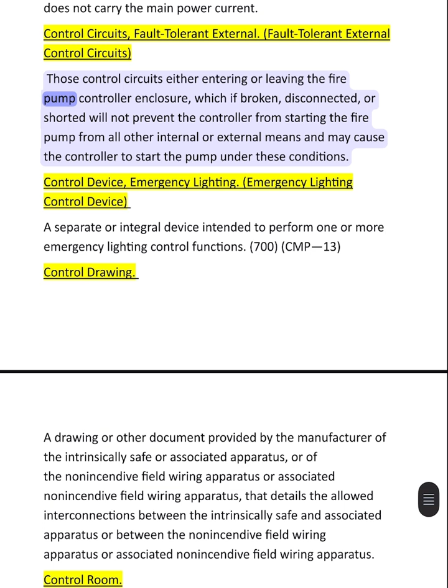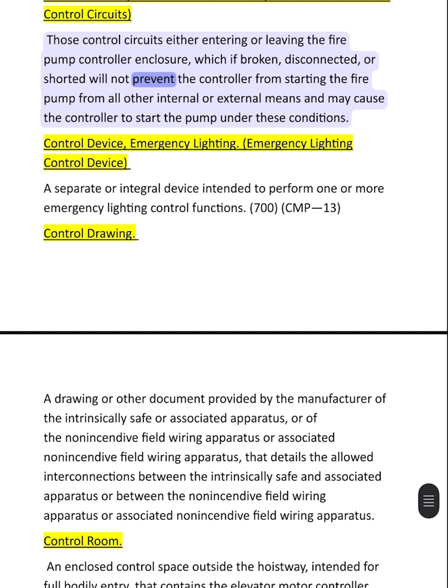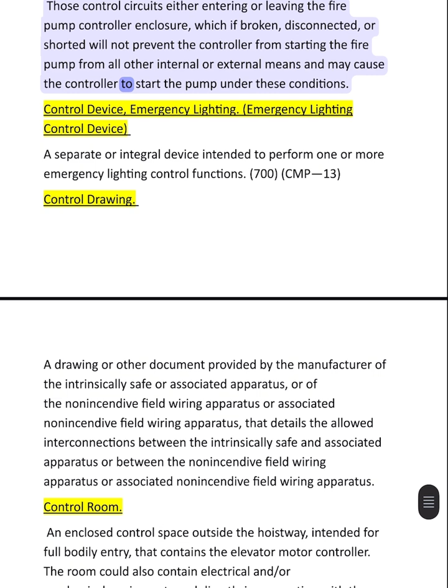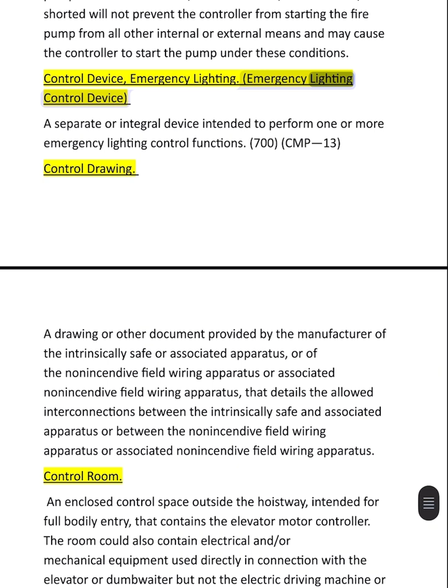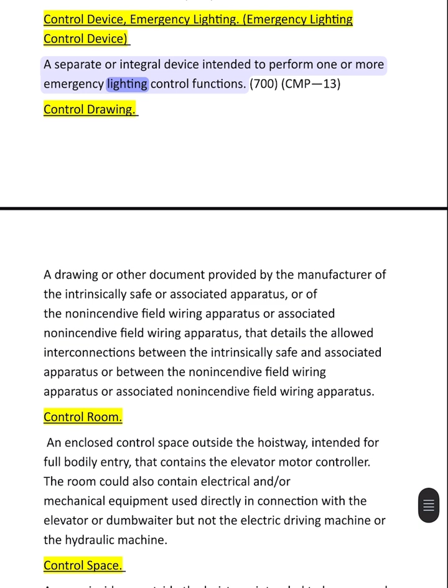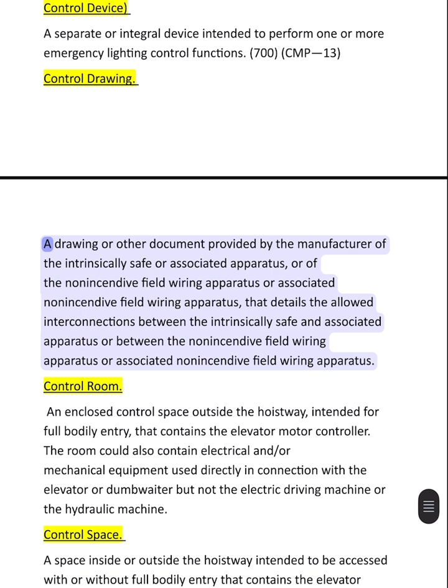Those control circuits either entering or leaving the fire pump controller enclosure, which if broken, disconnected, or shorted will not prevent the controller from starting the fire pump from all other internal or external means and may cause the controller to start the pump under these conditions. Control device, emergency lighting control device, a separate or integral device intended to perform one or more emergency lighting control functions. 700 CMP 13.